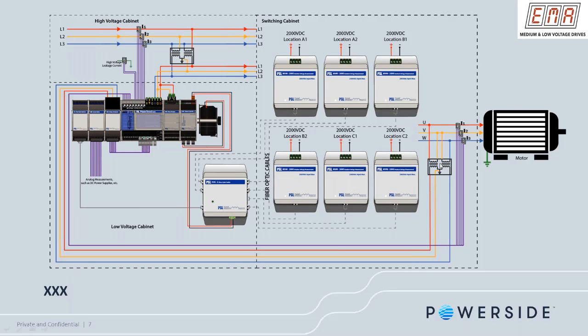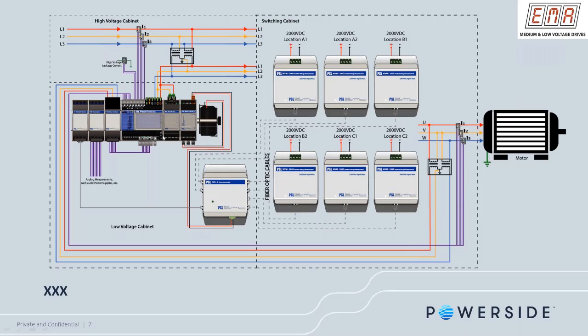And then on our output section, we have a similar configuration. We have PTs that are connected on our output, and then we send that back to our drive scan. And then we have CTs that are reading our current on the output side and sending the output current to the drive scan. So with this configuration, we literally can know the health of the drive without actually opening the doors of a medium voltage drive, which in reality we cannot even do. It's not allowed by code to open those doors while power is applied to the VFD.